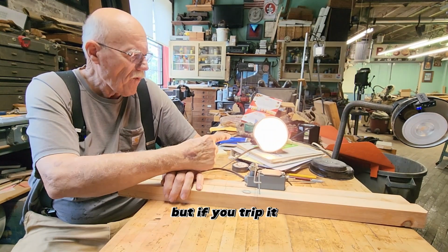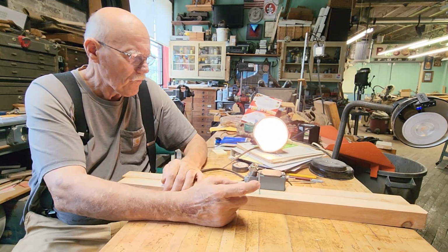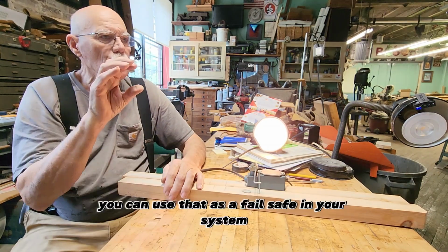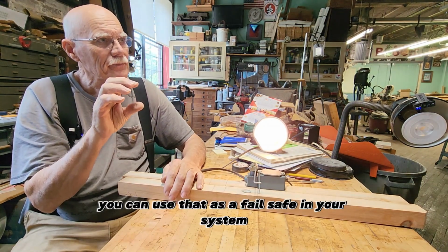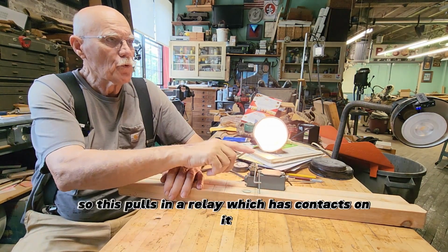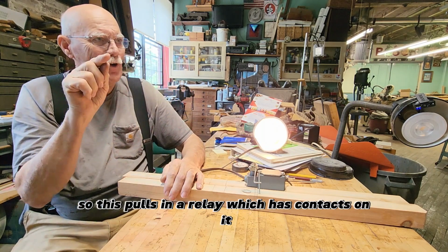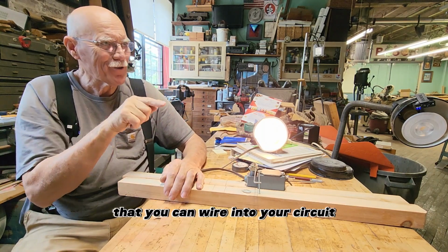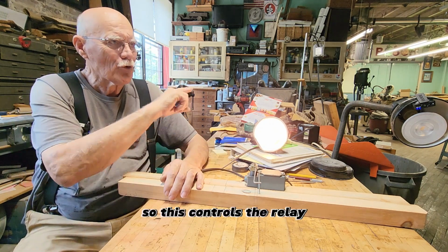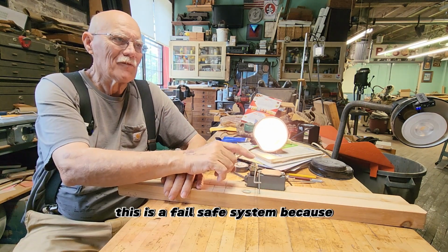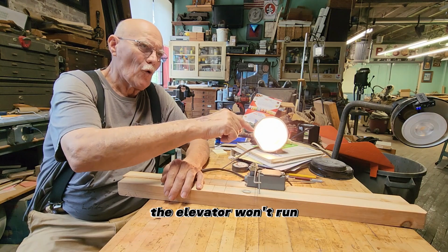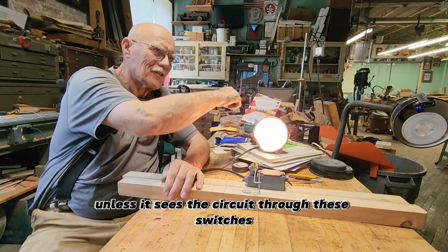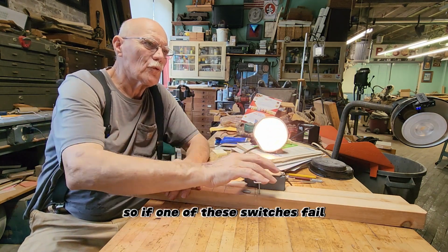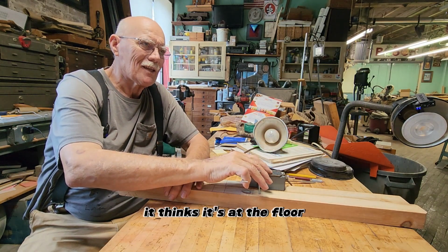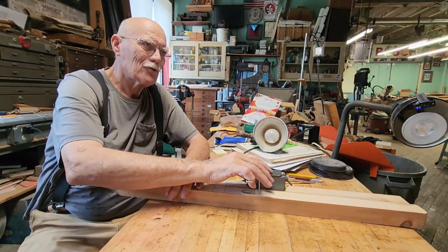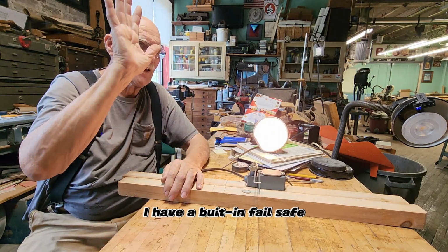But if you trip it, you can use that as a fail-safe in your system, so you can have a relay. So this pulls in a relay that has contacts on it that you can wire into your circuit. So this controls the relay. This is a fail-safe system because the elevator won't run unless it sees the circuit through these switches. So if one of these switches fail, it thinks it's at the floor and it will stop. So I have a built-in fail-safe.